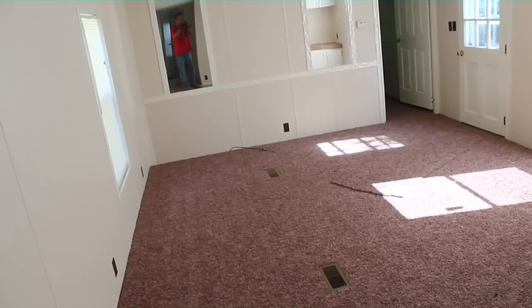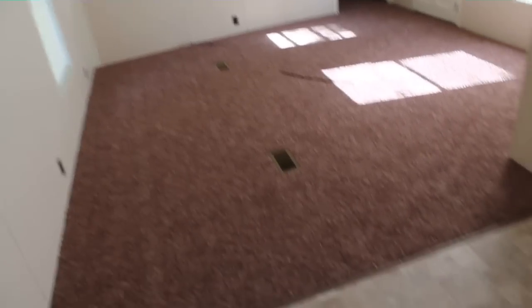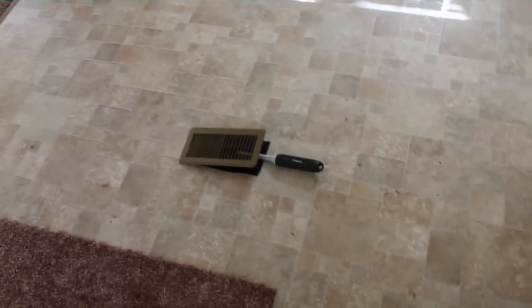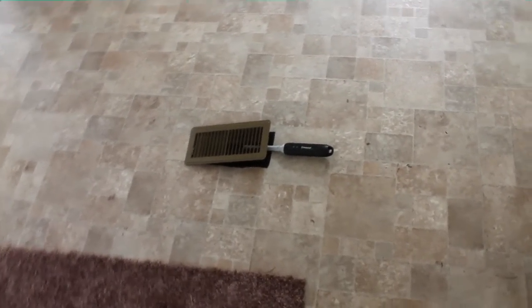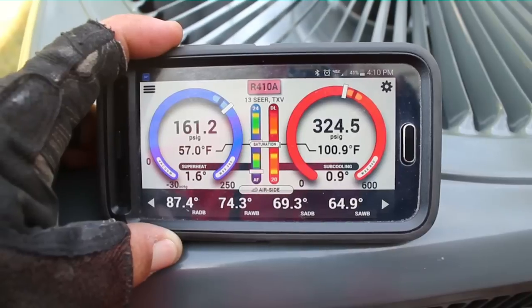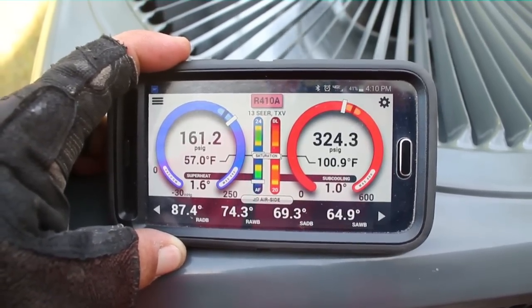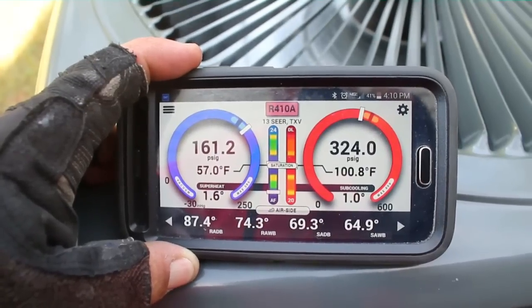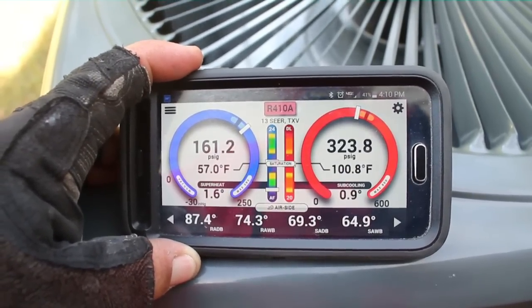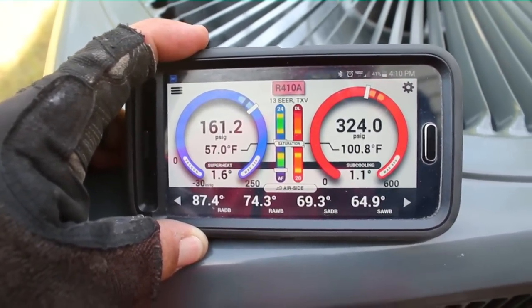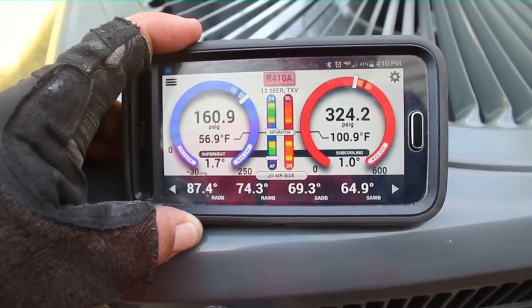But I'm gonna head back outside. We're putting refrigerant in the machine and should be wrapping it up here shortly. We'll let it run for a while, but everything's going well as we just got done putting in the 11 pounds of refrigerant. We have our return air temperature dropping down pretty steadily. We have 1.6 degrees of superheat. We'll see if that comes back up. If it does not, we will adjust the TXV.